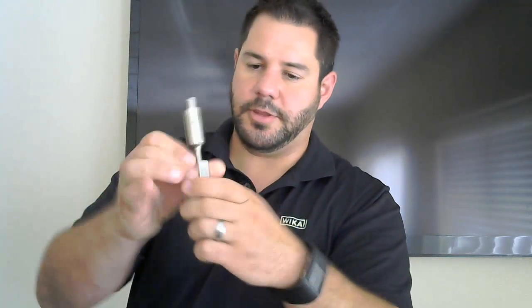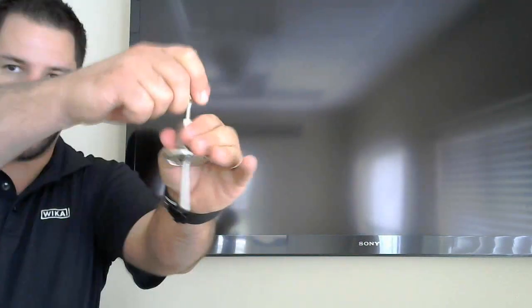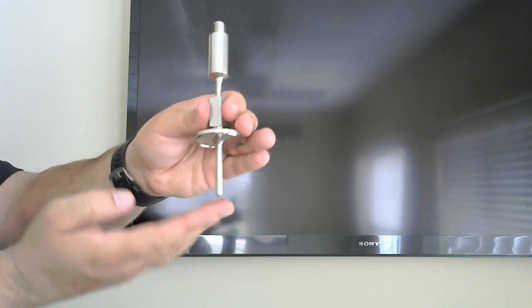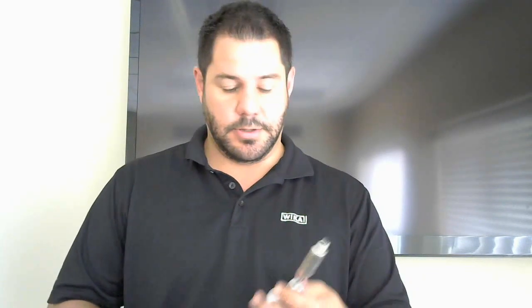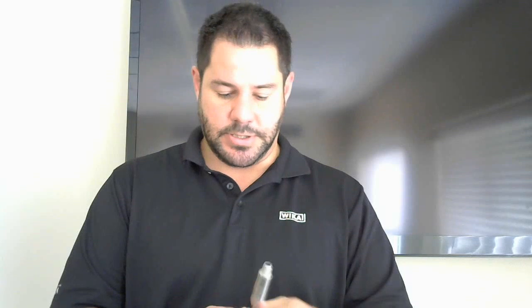It's spring loaded, so it constantly has contact with that bottom portion, giving you the most accurate reading. These can be done anywhere from 3/4 of an inch up to, I want to say, 4-inch tri-clamp. These come in a wide range of sizes.